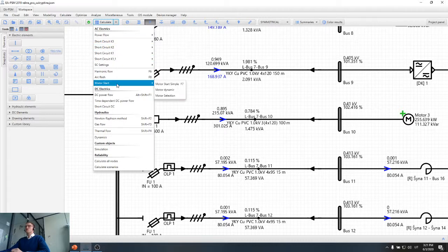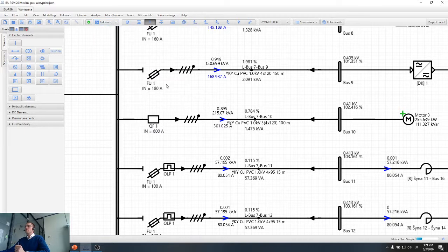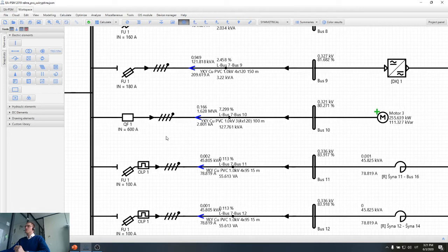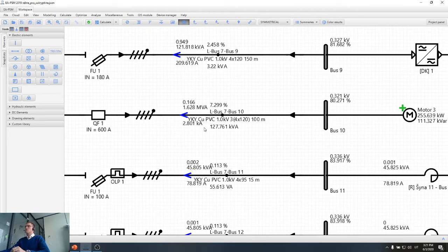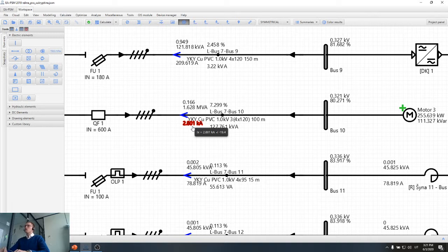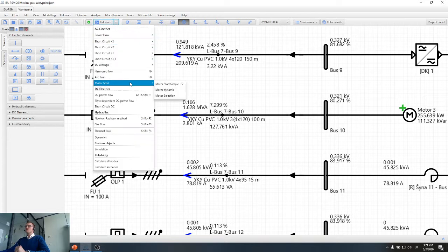Then we also need motor starting, which is a tool that allows us to estimate the currents flowing in the network during motor starting. You may remember that in this line during normal operation the current was about 300 amps, and during motor starting this current can reach up to 2.8 kiloamps, so 2800 amps. The calculation that I used here was simple motor starting. This is a more conservative calculation that usually gives a bigger motor starting current, and it also does not allow us to estimate the motor starting time.